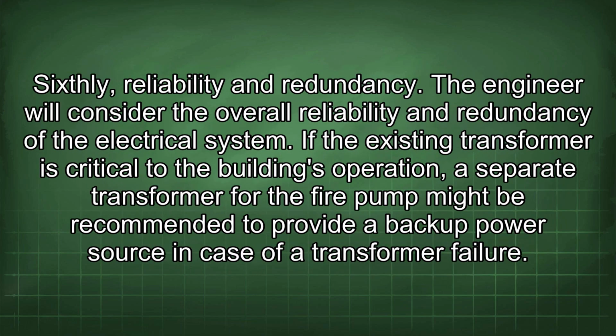Sixthly, reliability and redundancy. The engineer will consider the overall reliability and redundancy of the electrical system. If the existing transformer is critical to the building's operation, a separate transformer for the fire pump might be recommended to provide a backup power source in case of a transformer failure.